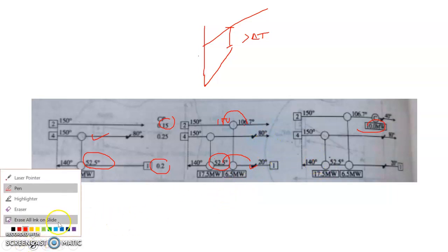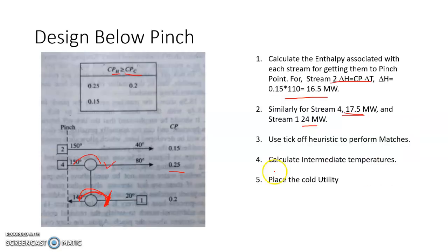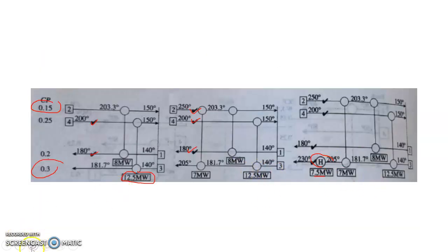You can design above pinch and below pinch separately, but the combined network must show all intermediate temperatures. A tick mark on a stream means it is satisfied in one exchanger directly from pinch to target temperature. Two exchangers for a stream means an intermediate temperature must be shown. This was a simpler example; we will look at more complex heat exchanger network design examples using the pinch design method in upcoming videos.